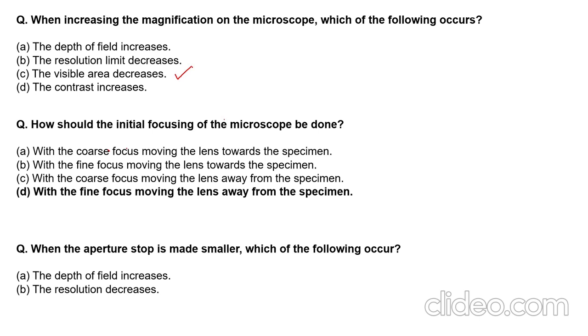Fine focusing this way means you move the sample away from the lens. That is the ideal way, because otherwise the specimen will be crashing into your lens. So to avoid that, you should do the fine focusing first and then keep it away from the specimen.